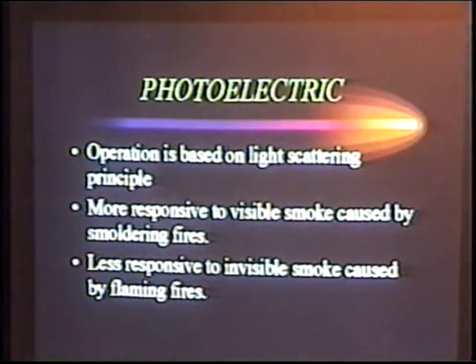We have a detector, and inside that detector we have a light source and a photo sensor. We do not want to aim the light source at the sensor itself. Once we bring a particle of smoke in there, it interrupts the light source, creates a flickering, or basically a reflection. That reflection is then reflected back onto the sensor inside the smoke detector, which generates the alarm off the flickering of the reflection of the light.